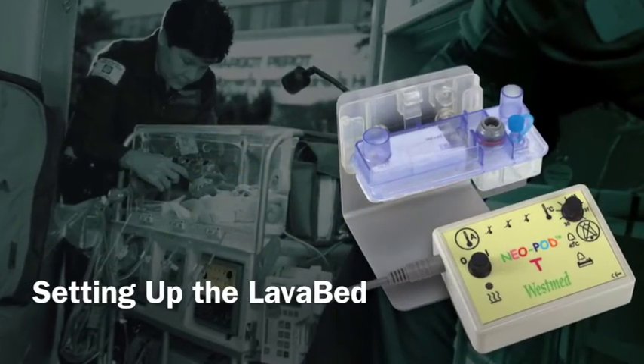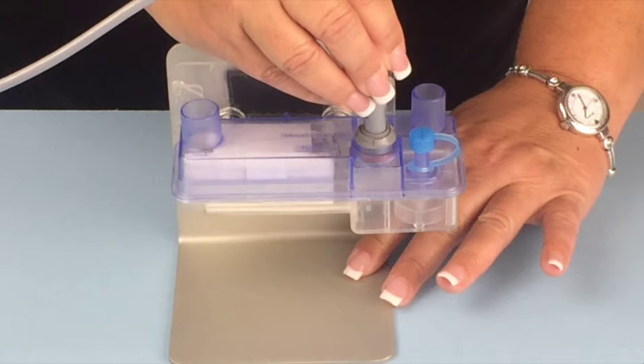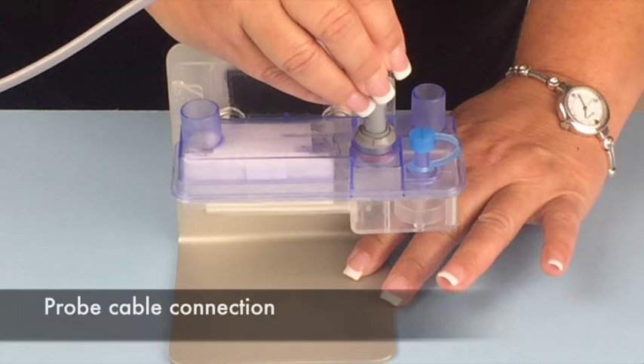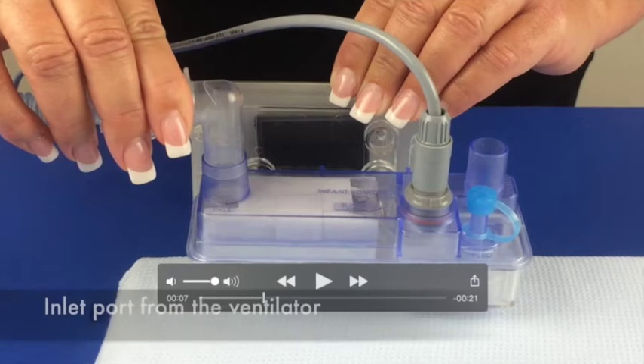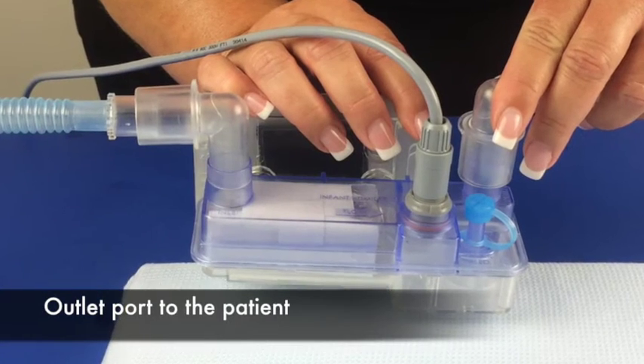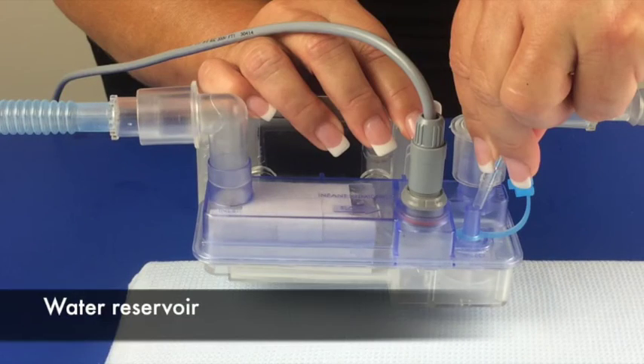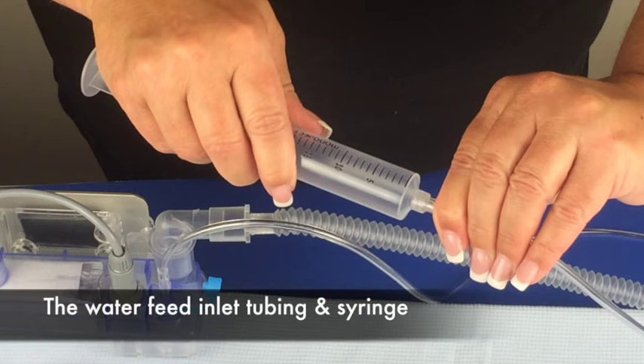Setting up the LavaBed chamber and circuit. The LavaBed chamber has several connections to be made: the LavaBed probe connection, the inlet port from the ventilator, the outlet port to the patient, the water reservoir, and the water feed inlet for adding water.